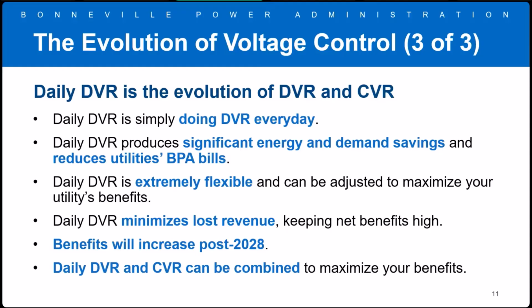This produces significant energy and demand savings, and importantly, it reduces utilities' BPA bills—that's where most of the value comes from. It's extremely flexible and can be adjusted to maximize benefits for each utility. This isn't a one-size-fits-all program; it can be targeted to the time of day or time of year. Any time a utility has a need, DVR can be targeted to address it. It also helps minimize lost revenue compared to CVR, because it only targets times when prices or need are high, not when need is lower—minimizing the lost revenue utilities experience with CVR.